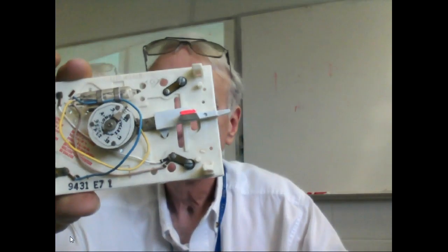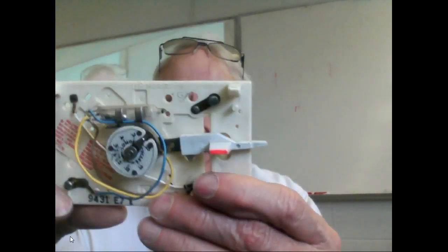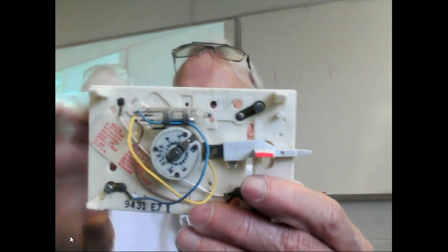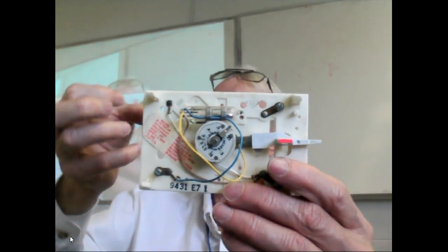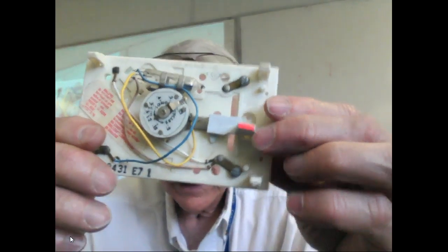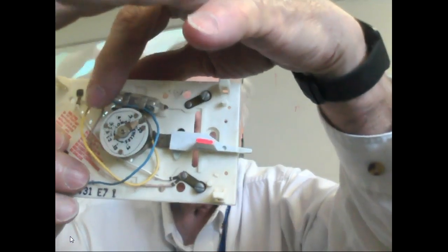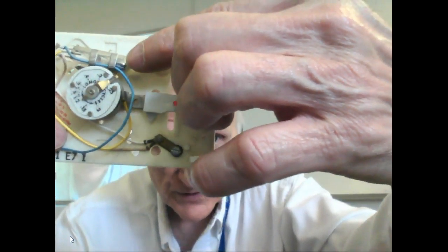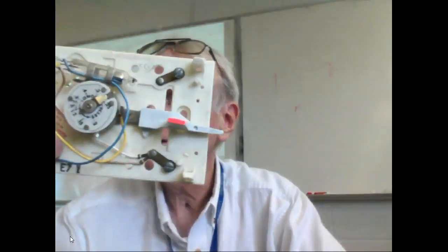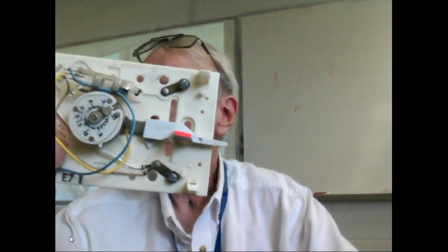mercury switch. I would set my temperature, and I'm either going to make the coil tighter or loosen the coil up with this right here. Then when it heats, this thing would come up here and start tilting. Depending on which direction it is, there's a contact up here at the end. I'm going to pass this around. Don't drop it because it's mercury, right? If you broke it, you'd have to pick it up.